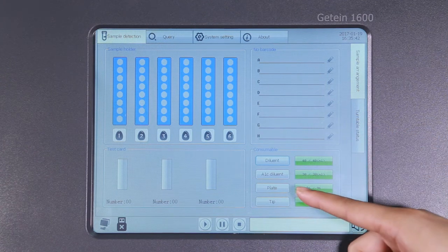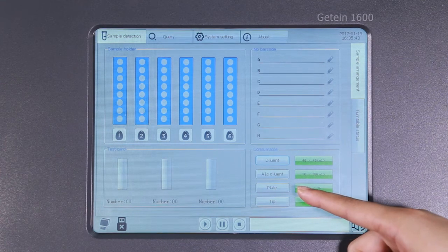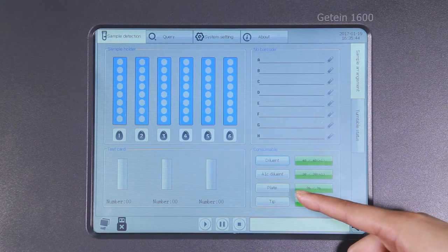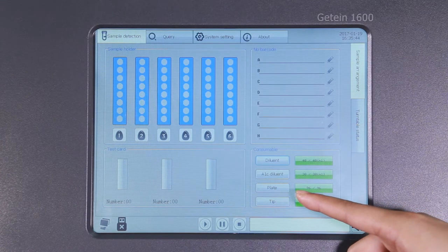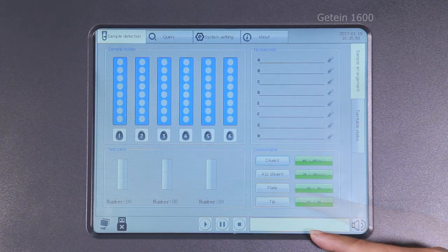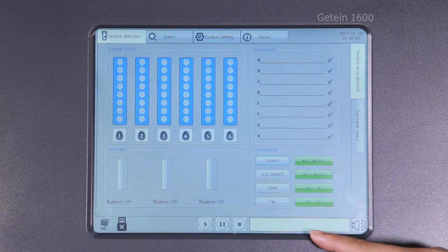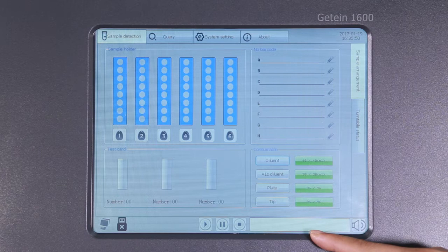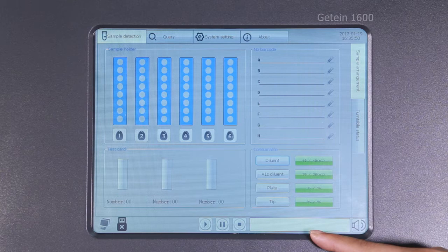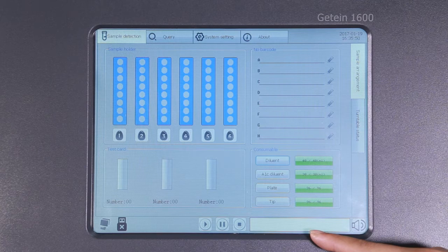On the right side of the touch screen are sample bar codes and numbers of remaining consumable supplies. The information should be confirmed after the consumables are replaced. The empty rectangle bar next to the operation keys is for error display. Weekly operational error information will be automatically shown in the bar. Click to trace error details.